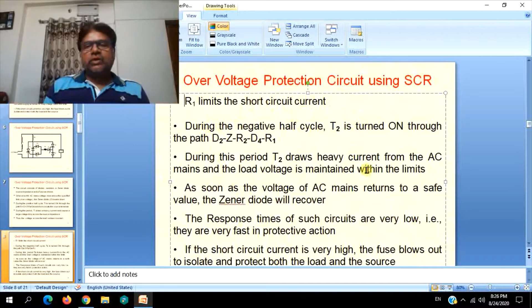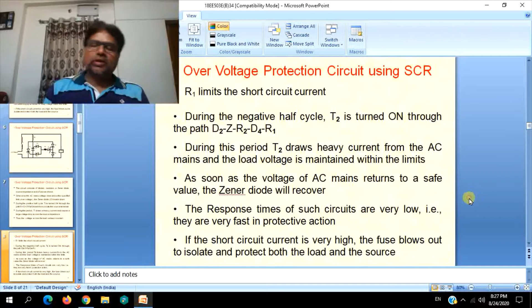The response times of such circuits are very low owing to the faster turn on times of the SCR. They are very fast in protective action. If the short circuit current is very high, then only the fuse blows out. So the turn on times are among the ratings of the SCR. The current ratings of the SCR should be more than the fuse ratings. So that is how the over voltage protection circuit using SCRs will operate.